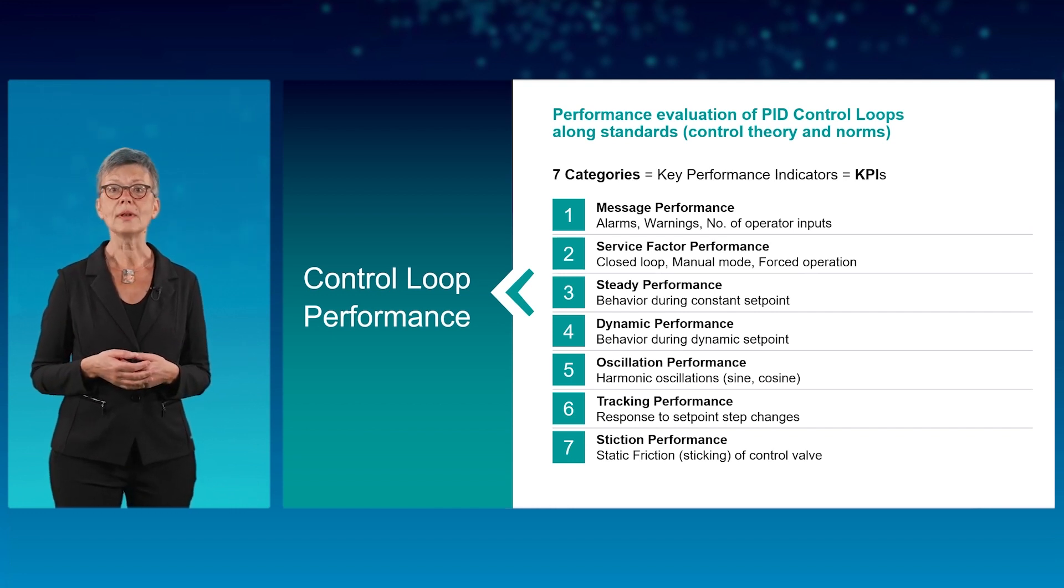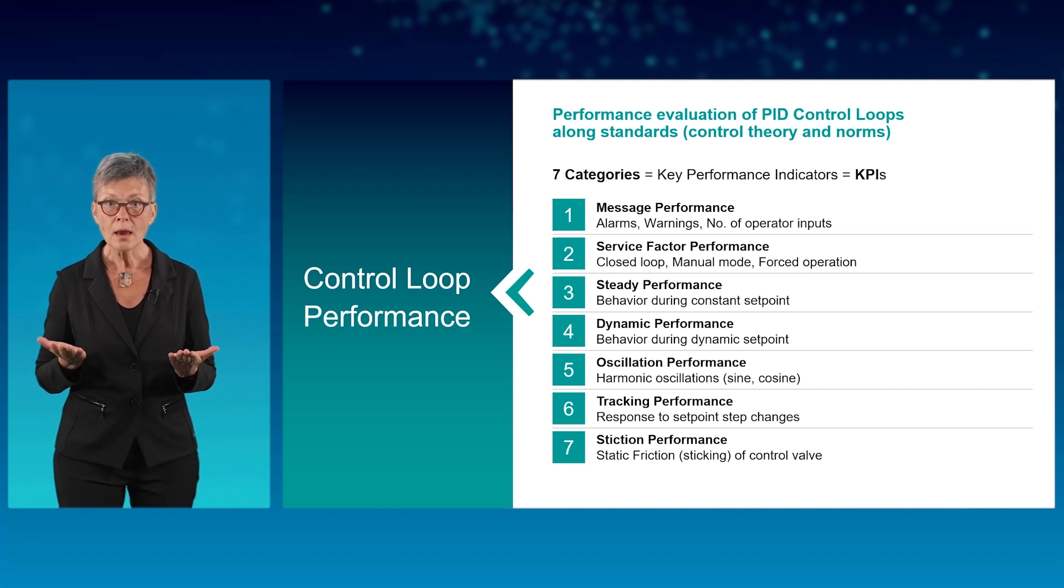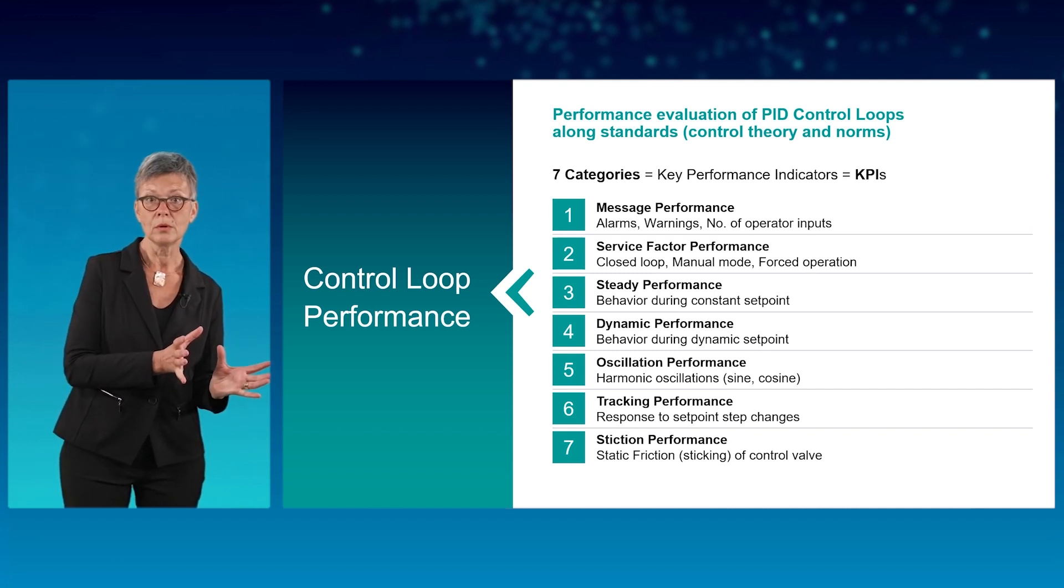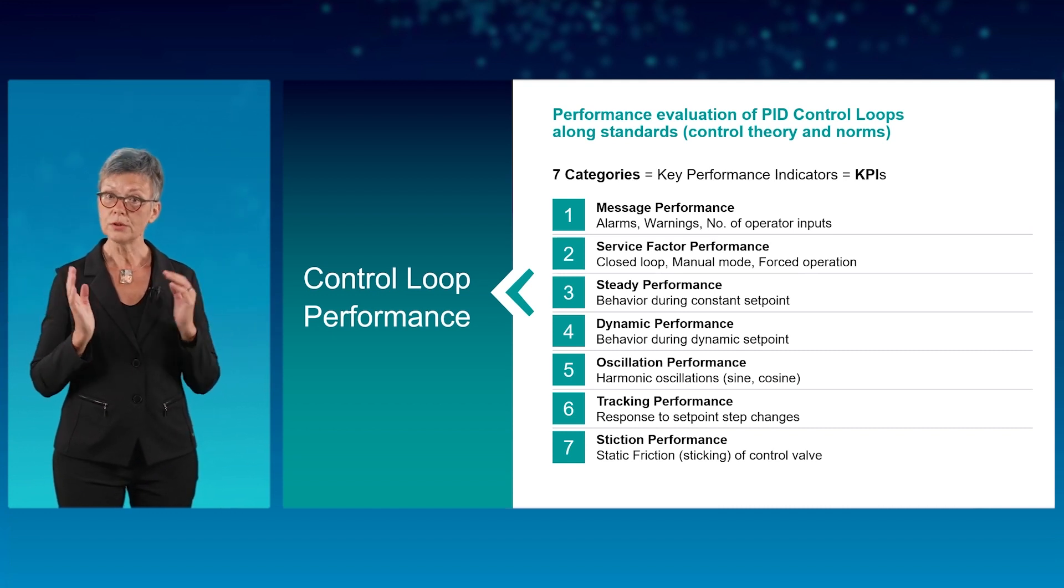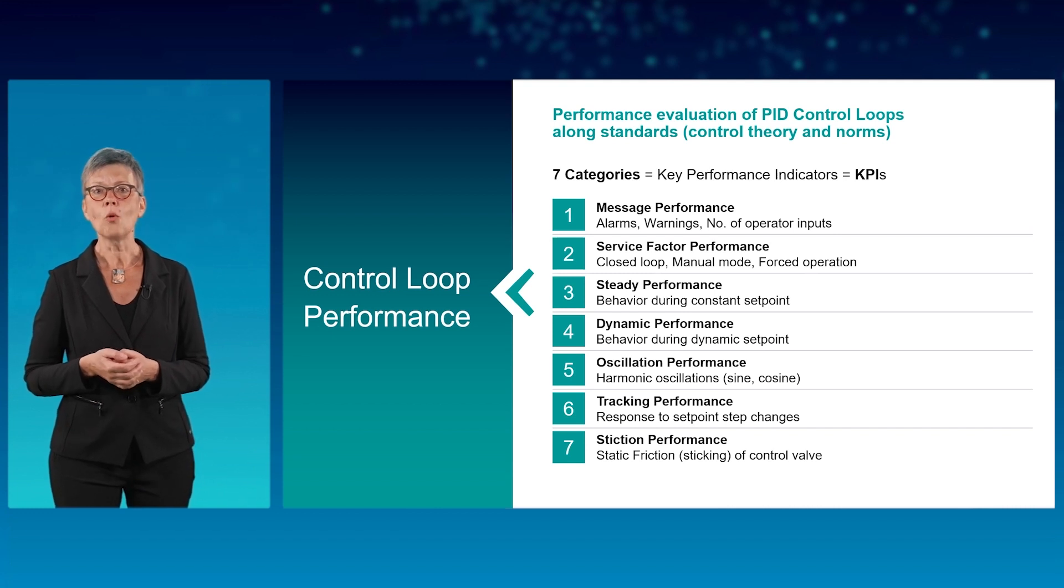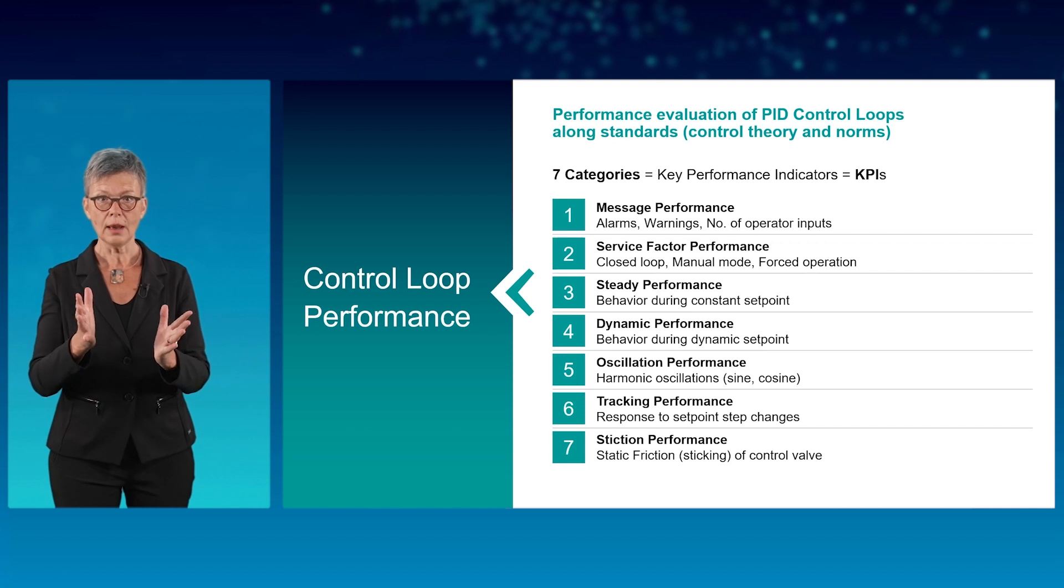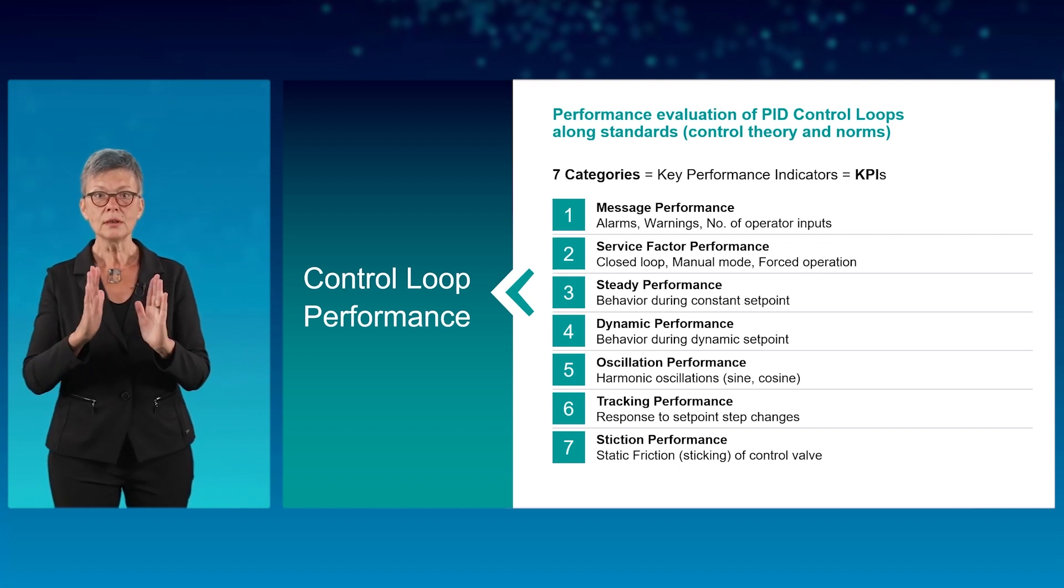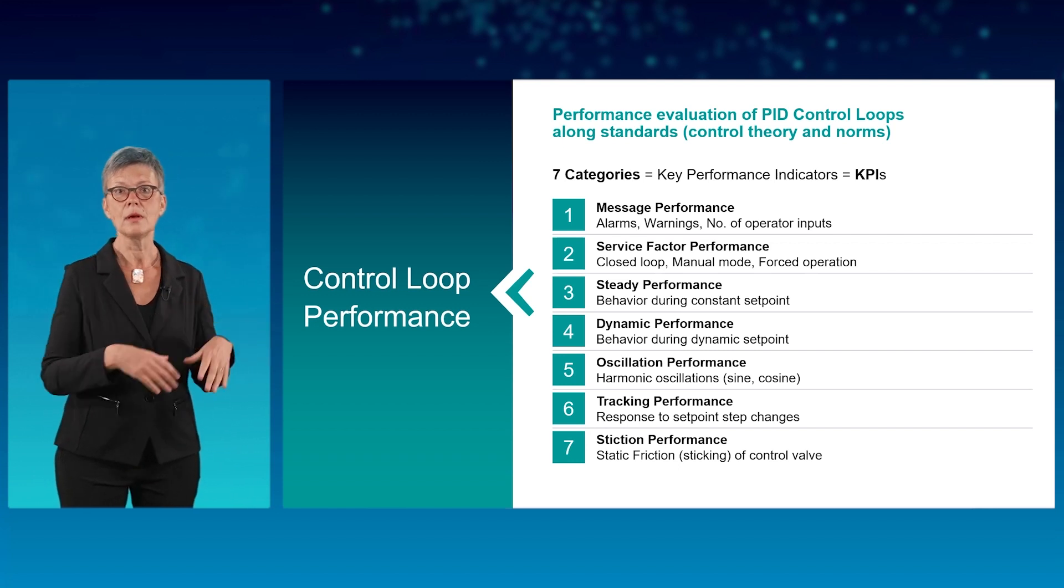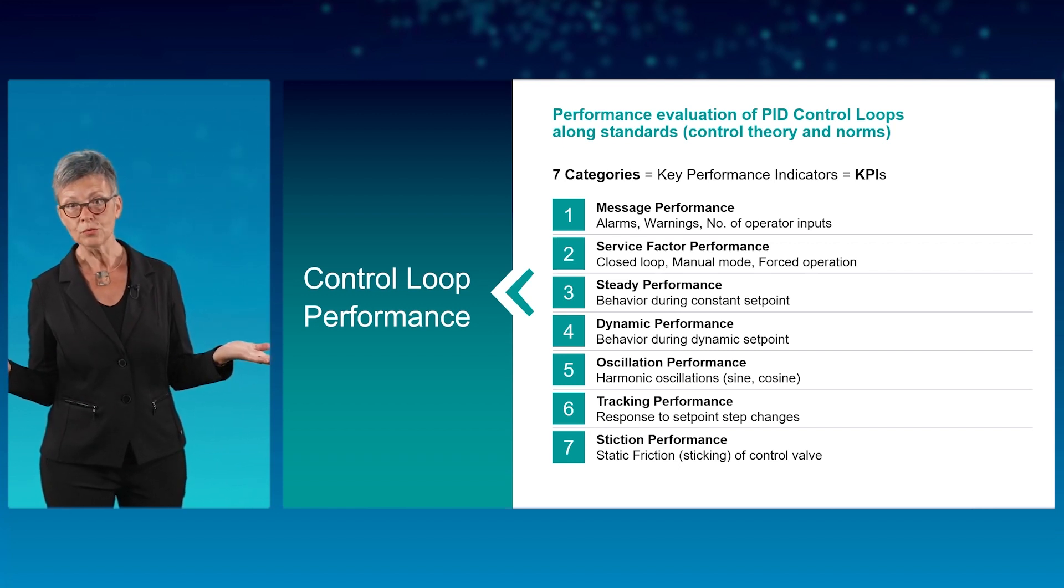For example, a loop that is often in manual mode may indicate that there is a problem with a loop. Check back with the operator and you might find an opportunity for improvement. But of course, CPA can go much deeper than that. You can systematically drill down and check out behavior of the individual loops at different periods of time. CPA has it all readily prepared for you.